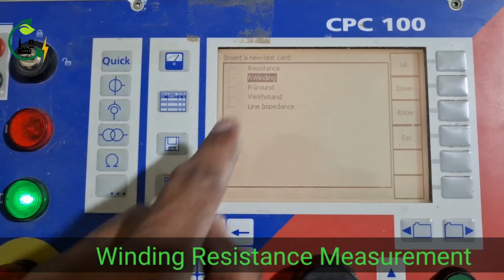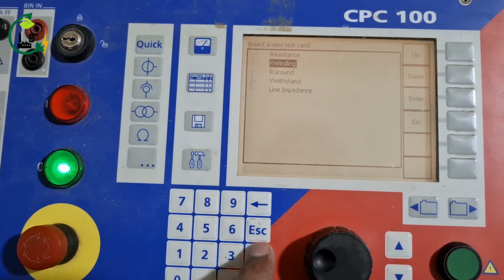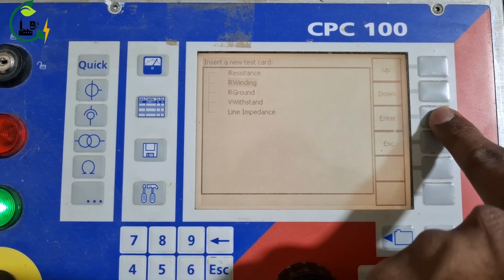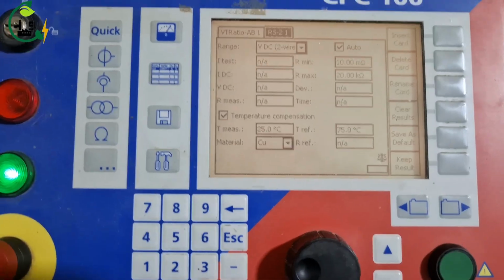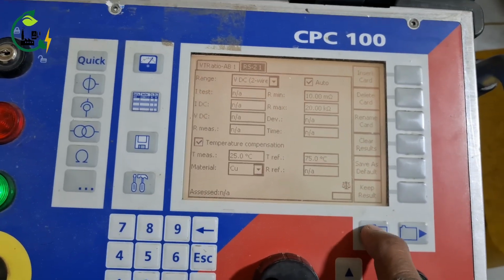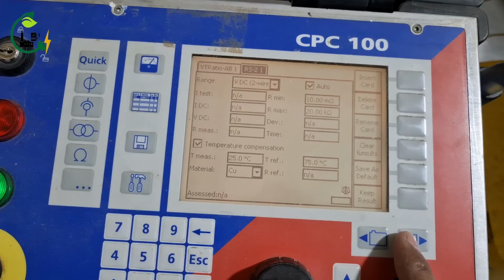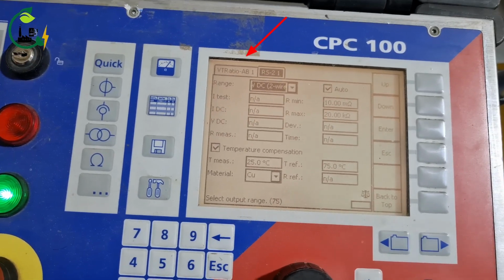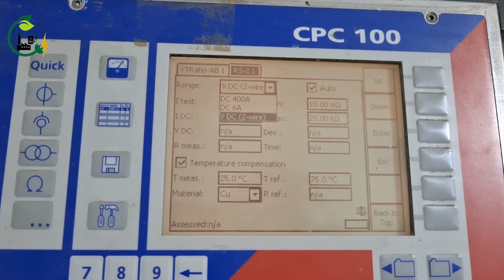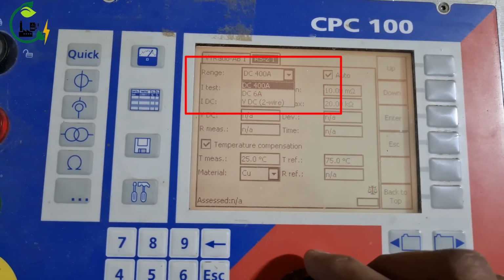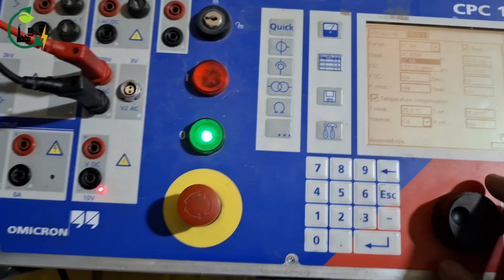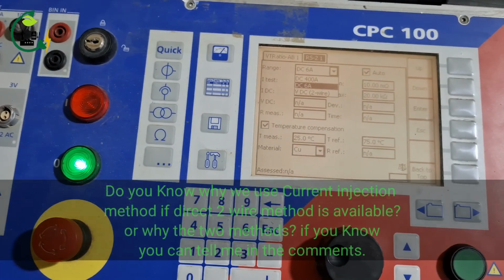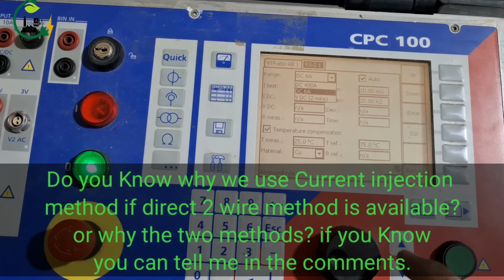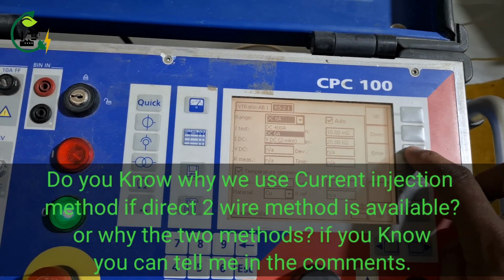So we will go into the resistance page and then into the R winding. When we enter the R winding, this page will appear. To check the winding resistance of the secondary and primary, you can create different pages to make one complete report for the VT. Here you see for the winding resistance we have 2 methods: current injection method and direct 2-wire method. First I will tell you the current injection method, and after that the 2-wire method. Why we use the current injection method and why we use the 2-wire method, I will tell you.